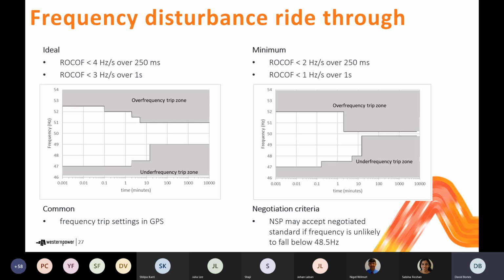The common requirements that are specified require the GPS to record any relevant frequency trip settings. So it's obviously quite important, if you're saying that you're going to be able to avoid tripping at a particular frequency, to actually then record the frequency settings at which you are programmed to disconnect. And the negotiation criteria, so guidance is given there that the NSP must consider whether the frequency is likely to fall below 48.5 when it's considering whether to accept the relaxed standards specified by the minimum performance standard.